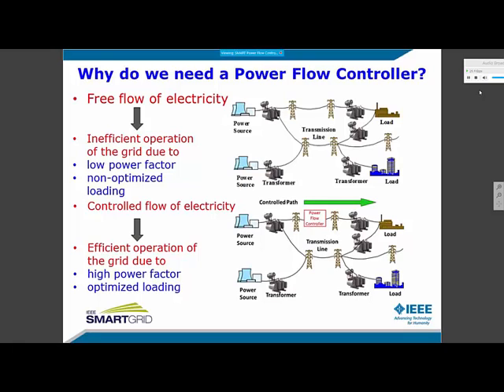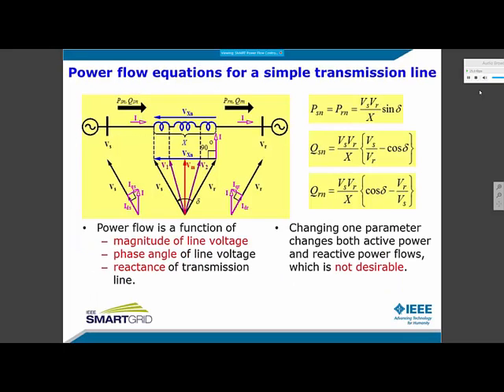If we represent the power grid in a simple manner with a voltage source at the source end and a voltage source, maybe the back EMF of a motor, at the load end, and the line just an inductive reactance to represent a basic simple power system, the power flow equations show that both active power P and reactive power Q at both ends of the line are sine and cosine functions. The power flow controlling parameters are voltage, the phase angle of the voltage, and the line reactance. Changing one of these parameters changes both P and Q flows simultaneously, which has been the traditional technique of power flow control since the beginning of electrical engineering.